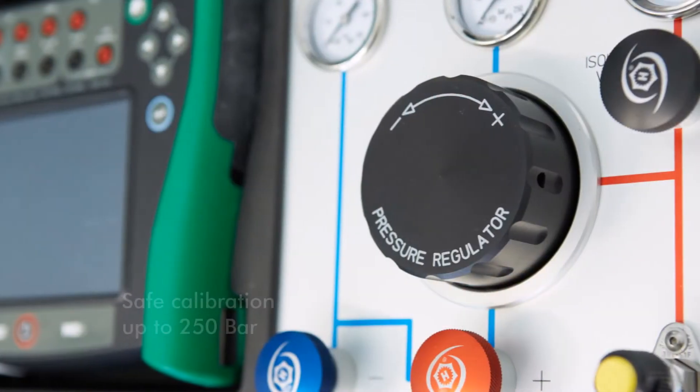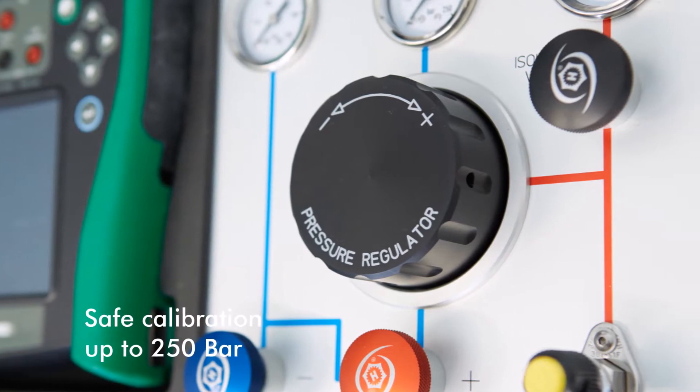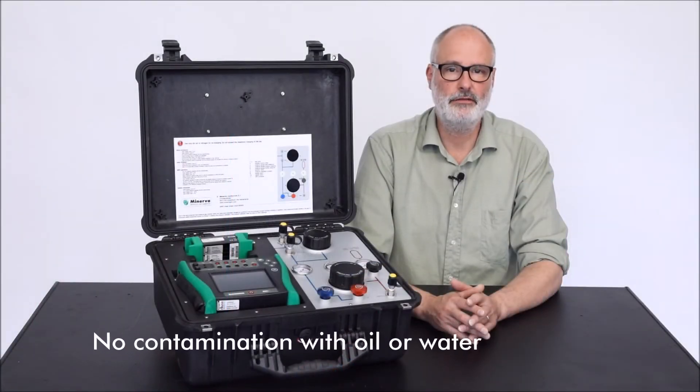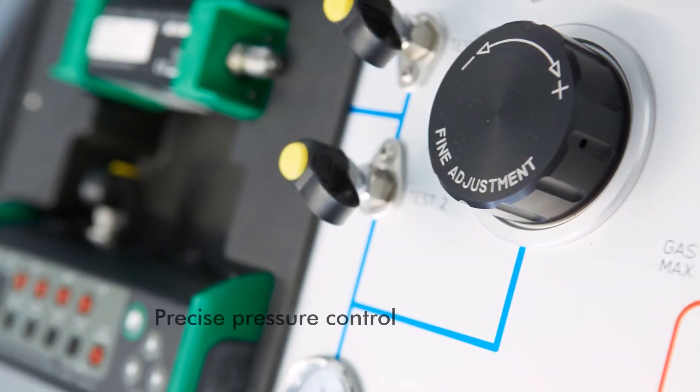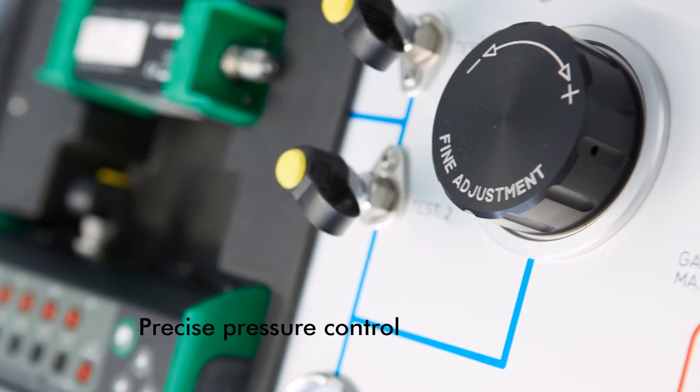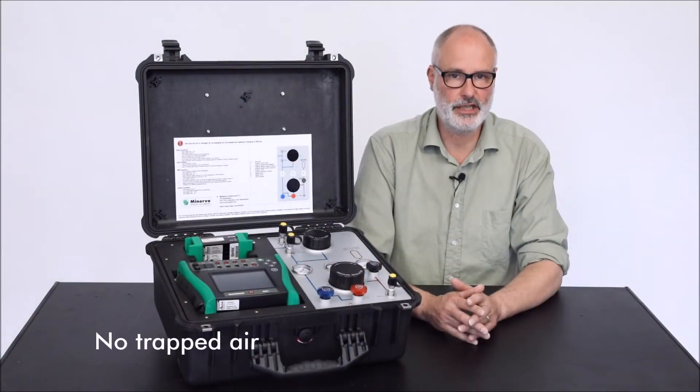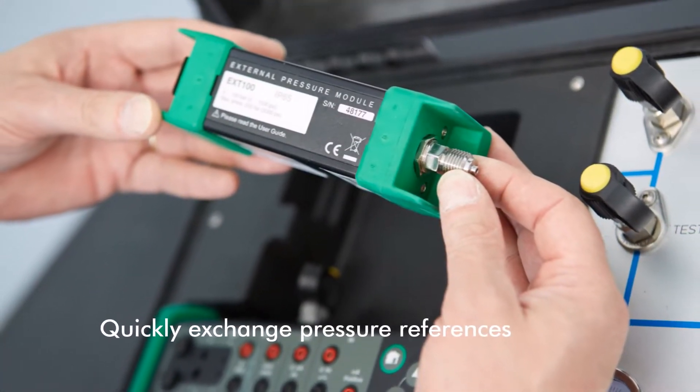It enables you to perform safe pneumatic calibrations up to a maximum pressure of 250 bar, not contaminate the device under test with oil or water, perform precise test pressure control using a pressure balance volume adjuster, eliminate trouble with trapped air in a hydraulic system, and exchange calibrator pressure references quick and easy.